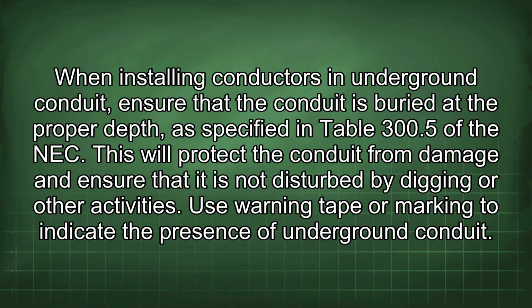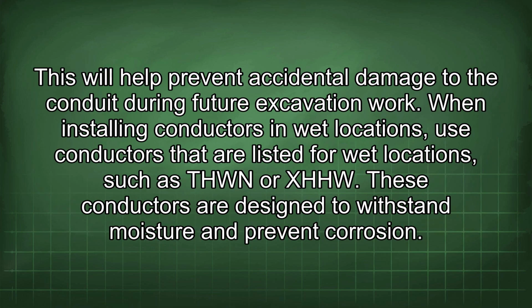This will protect the conduit from damage and ensure that it is not disturbed by digging or other activities. Use warning tape or marking to indicate the presence of underground conduit. This will help prevent accidental damage to the conduit during future excavation work. When installing conductors in wet locations, use conductors that are listed for wet locations, such as THWN or XHHW. These conductors are designed to withstand moisture and prevent corrosion.